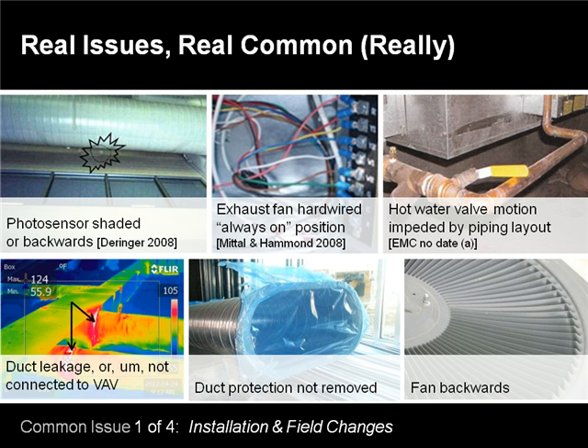Photosensors shaded. We also see sensors, and when somebody walks down the hallway, the office lights that are empty go on, and instances with the electrical side. We also see things that are wired incorrectly and they operate all the time. Exhaust fans that are just hardwired and operate 24/7, 365. Then the next picture, you're looking at a hot water valve that cannot be shut off unless you're going to take that handle or bend it to get it out of the way.